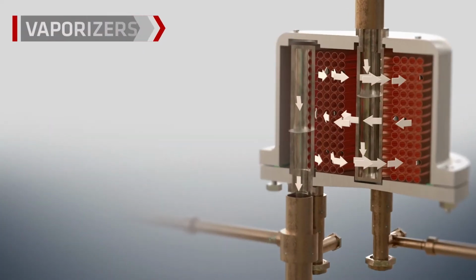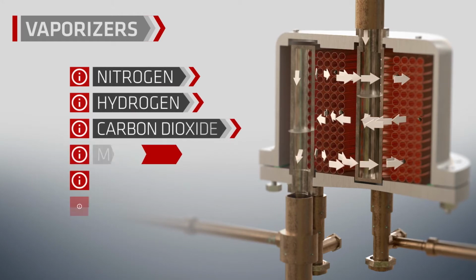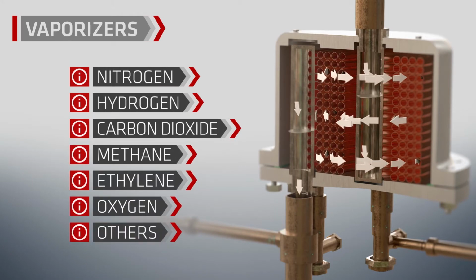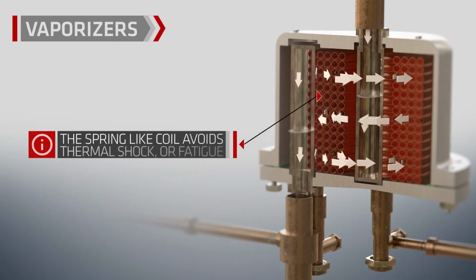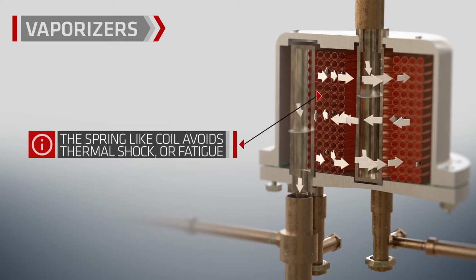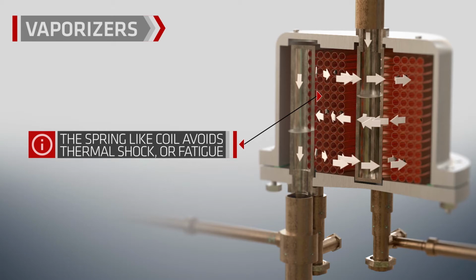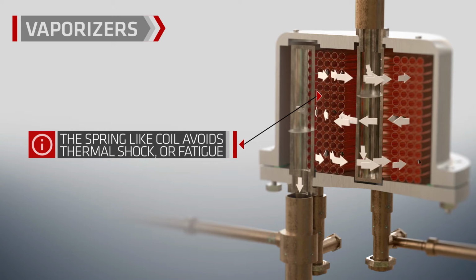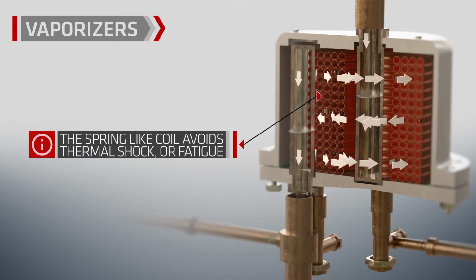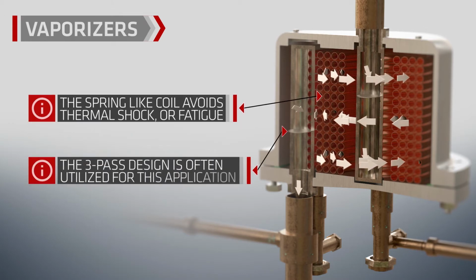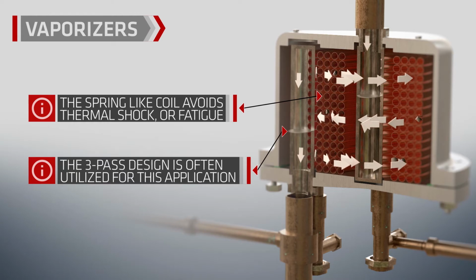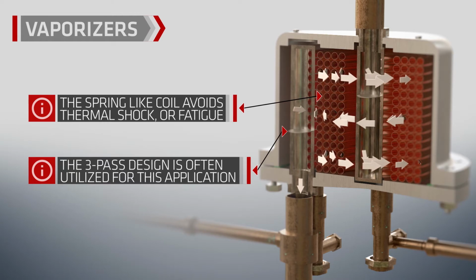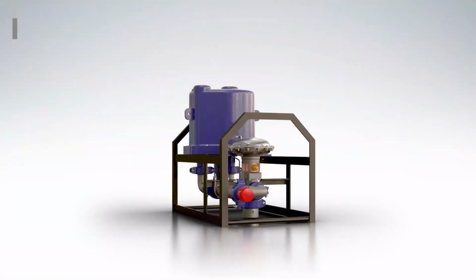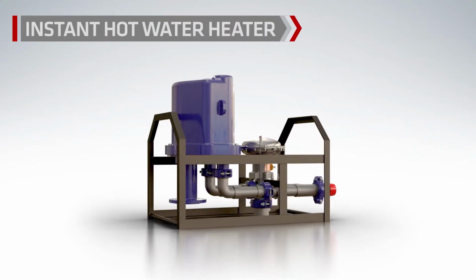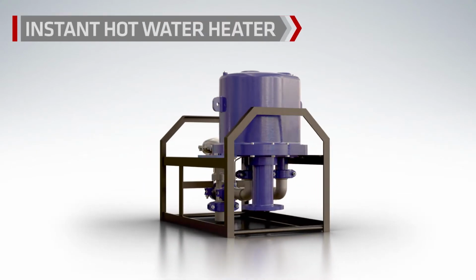Any industrial gas that is supplied and stored in liquid form, such as nitrogen, hydrogen or carbon dioxide, can be vaporized in the Heliflow. The spring-like coil mitigates risks of damage from thermal shock or thermal fatigue because the coils can expand and contract as the temperature changes without stressing the shell or connections of the heat exchanger. A 3-pass tube side is often used in vaporizing applications to maximize heat transfer rates while maintaining a compact footprint. The Heliflow heat exchanger can also serve as a highly efficient instantaneous hot water heater.